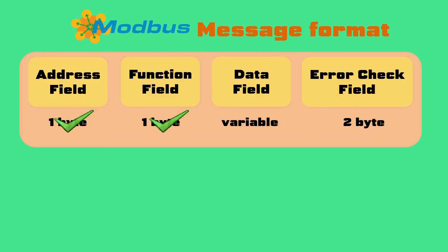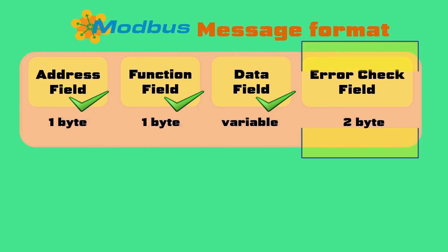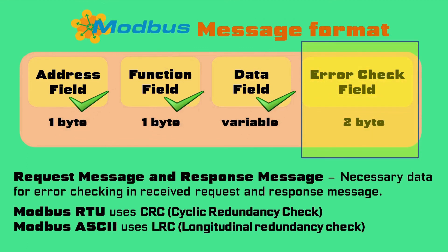The third field in a message frame is the data field, which may be of variable length. In the request frame, this field contains information that the targeted slave controller may need to complete the requested function. In the response frame, this field contains any data requested by the master. The last two bytes in a message frame comprise the error check field. Modbus RTU uses CRC while Modbus ASCII uses LRC for error checking.